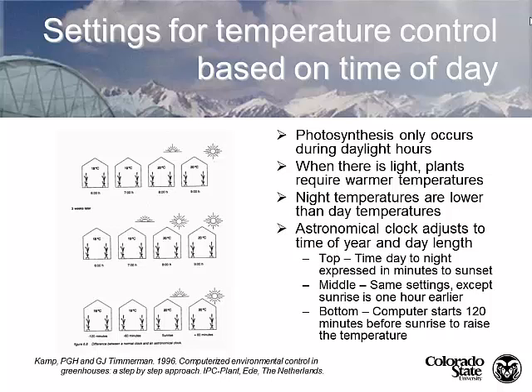In the old days we just used a time clock, but what's more important is the astronomical clock, because I'd rather do my heating and cooling based on whether the sun is out or not. Most greenhouse climate control computers have a set point for this. With systems like Wadsworth, one of the first things you do when setting up the climate control computer is entering the longitude, latitude, and how many time zones you are back from Greenwich Prime Meridian — for us that's minus seven hours.